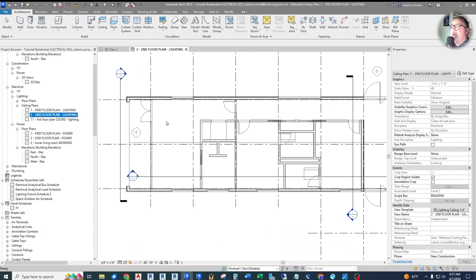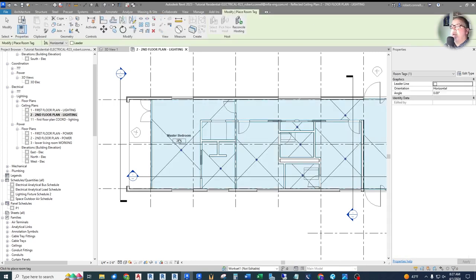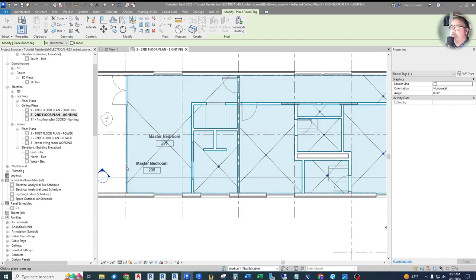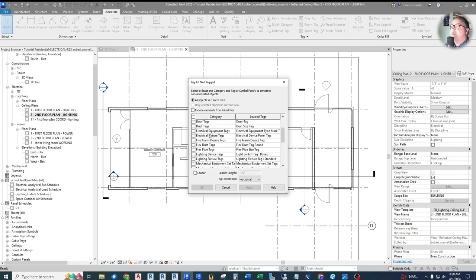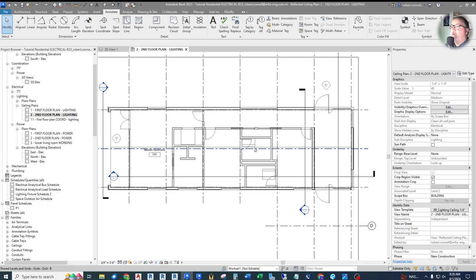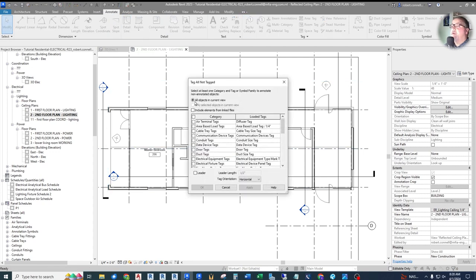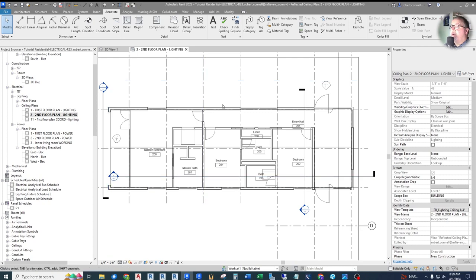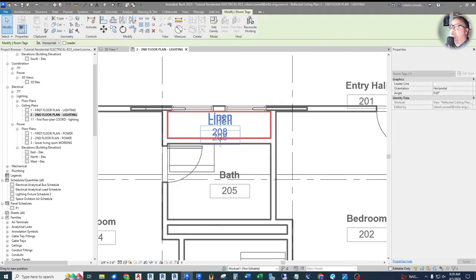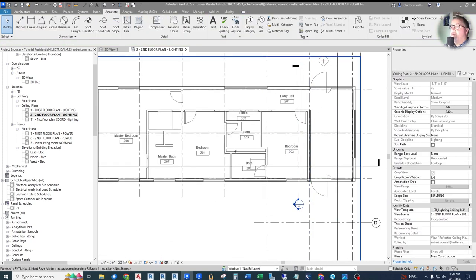Here's our blank second floor lighting plan. Let's add room tags like we did before: go to Annotate, then Room Tag. We've already set up rooms on the first floor, so now it's simply placing tags. You can also go to Annotate, Tag All, and check Include Elements from Linked Files since the rooms are in the linked architectural file — select Room Tags, click OK, and they all appear. They place in the center of each room and can be moved as we place lights.